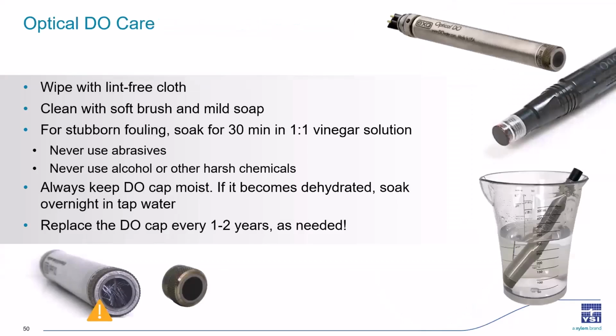Optical DO is going to have very different care and storage instructions from the membrane DO that we just went over. To clean off the debris, you're going to use a lint-free cloth and a soft brush and some mild soap to remove any buildup. If you need to remove tough fouling, you can soak the tip in a 1-to-1 vinegar solution for about 30 minutes. You're never going to want to use abrasives, alcohol, or any harsh chemicals on this sensor. Abrasives can end up scratching the black paint off that DO cap, which can let light in that will interfere with the measurement. If you notice that roughly 30% or more of the DO cap is scratched, you're going to want to go ahead and replace that.